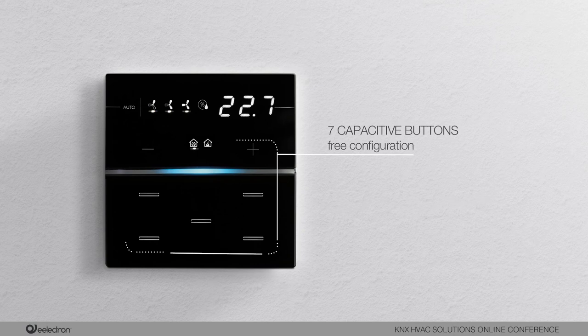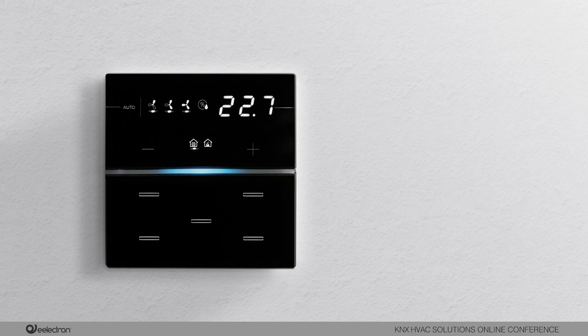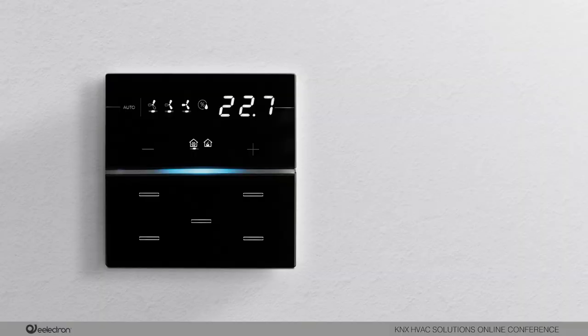The 1925 series is a complete solution of buttons, thermostats, thermostat plus humidity probe, and multi-controllers. The 1925 thermostat is a KNX room temperature controller with seven configurable capacitive buttons. It offers a two-stage thermostat with an integrated PI controller to control heating and cooling equipment, valves, two-pipe and four-pipe fan coils, and advanced equipment such as the six-way valve. It has an embedded temperature sensor, two-pole connectors configurable as digital or analog input, and supports an external NTC probe. A version with integrated temperature and relative humidity sensor enables dew point calculation and ambient humidity control.